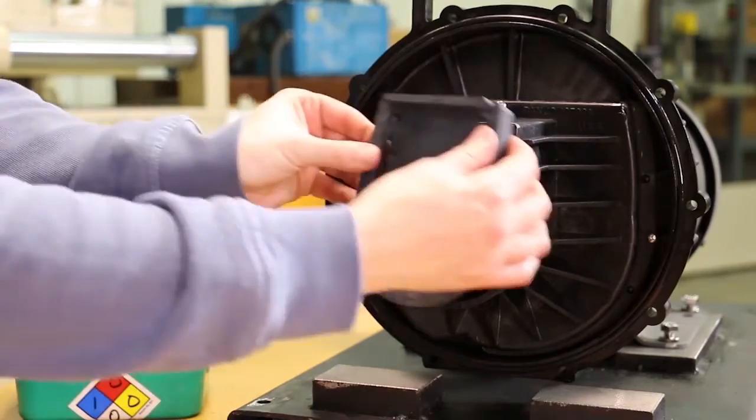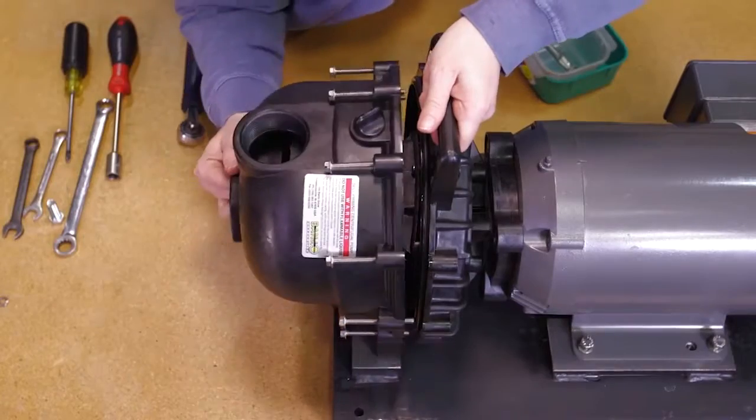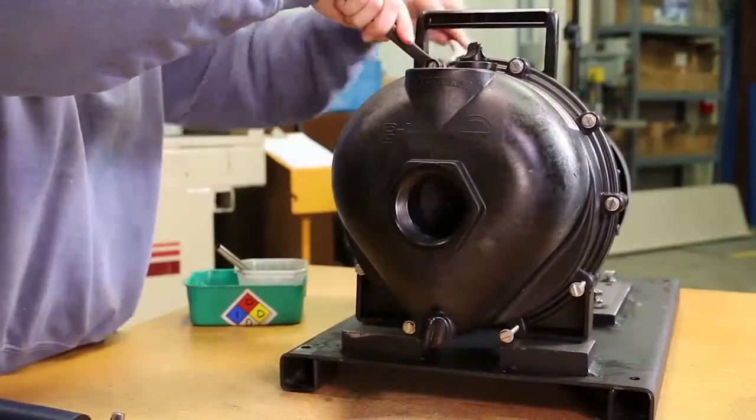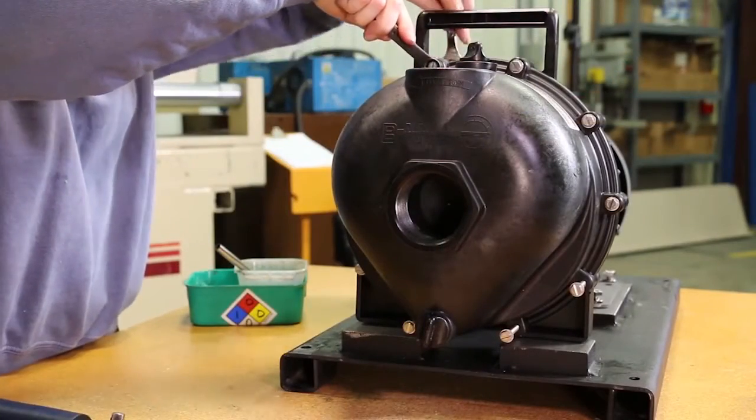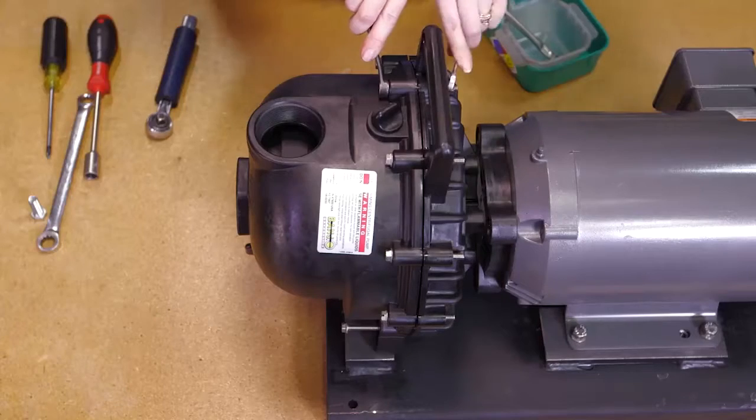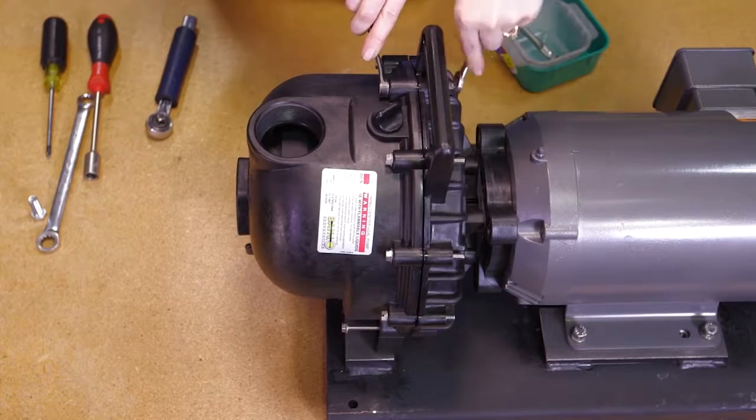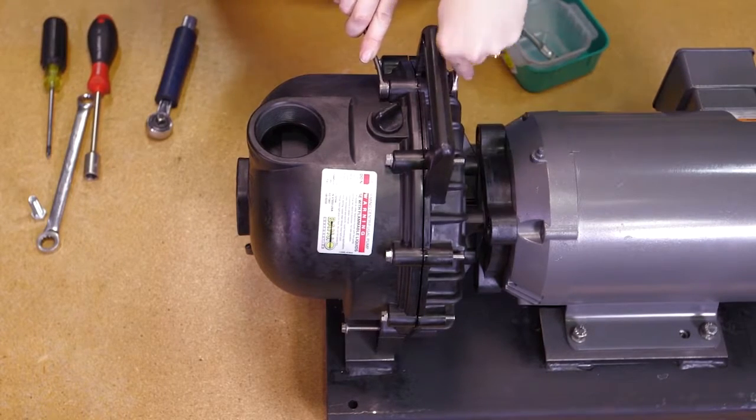Install the check valve onto the snout of the volute. Install the pump body with the outlet flange facing up. Install the ten body screws, lock washers, and nuts to secure the pump body to the rear bracket. Cross tighten securely all the way around.